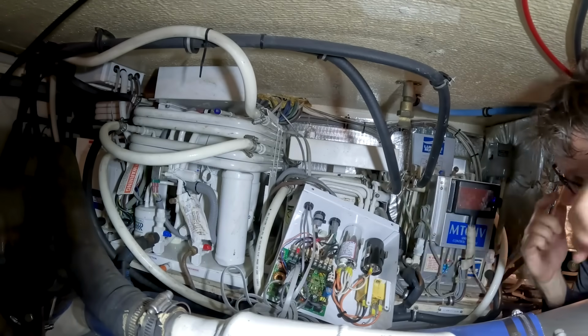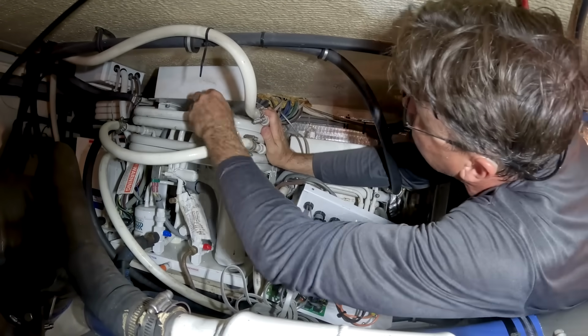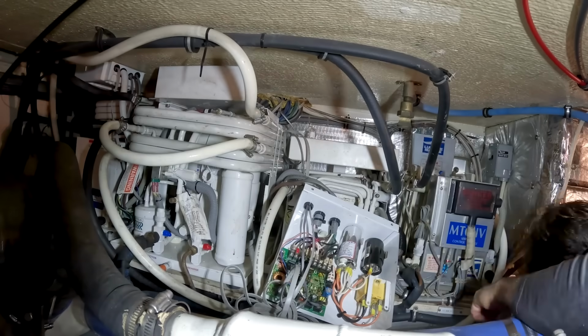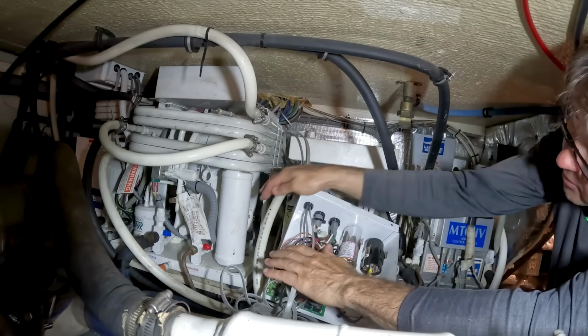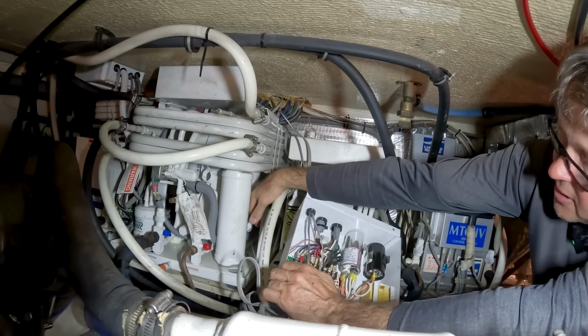Here we are back in our little hole. First thing I'm going to do is hook up to this guy right here. But before we hook up, we're going to depress this little valve in there and make sure salt water doesn't come out. We don't want salt water in my gauges. Nope, seems like good pressure. By the way, I ohmed out the common run and start leads, which are right behind this cover right here, and so the compressor checks good.